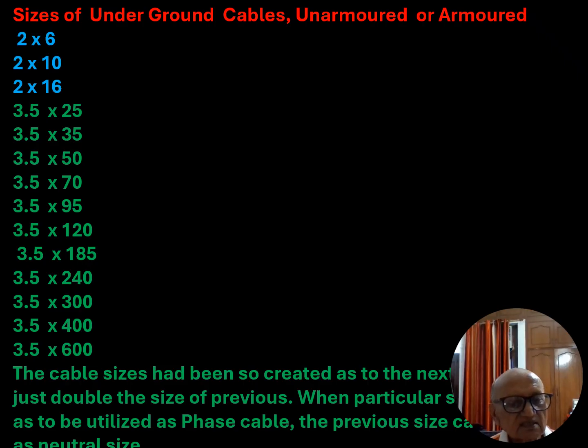Then the remaining cables are 3.5, 25, 35, 50, 70, 95, 120, 185, 240, 300, 400, and 600. These are always 3.5 core. That means 3 phase wire and 1 neutral wire, which is approximately half the cross section of the phase wire. Now we use these cables for TP and DB of several sizes and otherwise for MAN circuits. This is used in TP and DV of 3 phase, and the remaining are used for MAN wire, MAN cable.